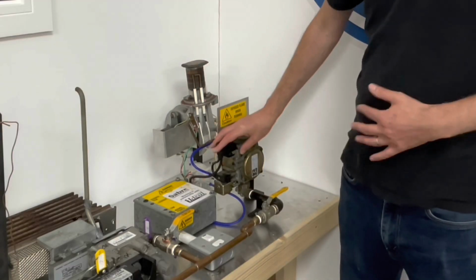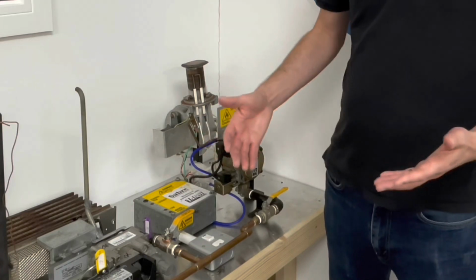The next two controls we're going to look at, again, work in conjunction with each other. We've got an air gas ratio valve or zero governor, and we also have flame rectification. So this is our air gas ratio valve, otherwise known as a zero governor.